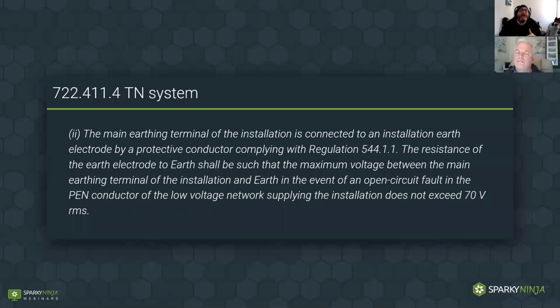The resistance of the earth electrode to earth shall be such that the maximum voltage between the main earthing terminal of the installation and earth in the event of an open circuit, again, this is the value here, does not exceed 70 volts. And you'd have heard this one, and everyone will say to you, you're not going to be able to achieve that value of voltage. But there's a good annex now, which is still there, but it's been updated.